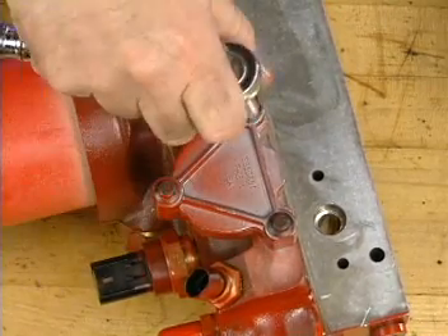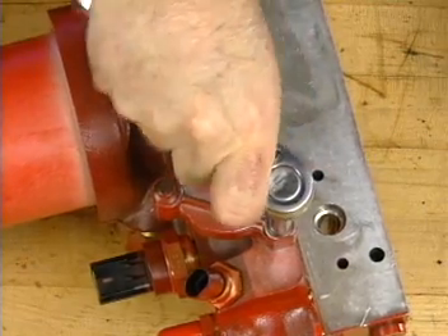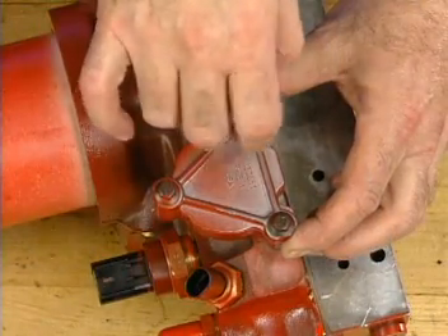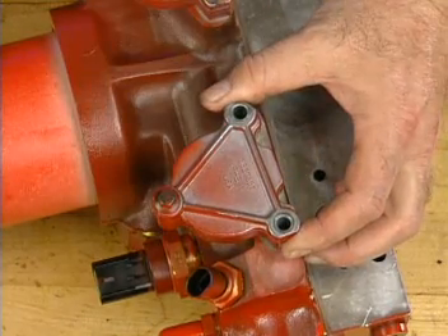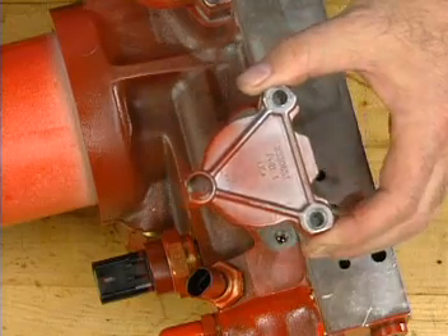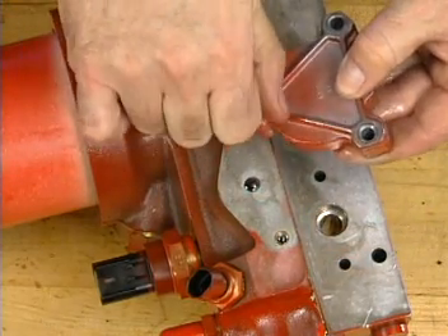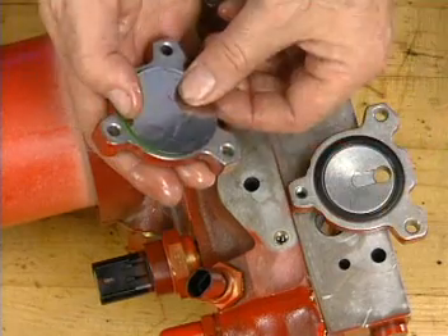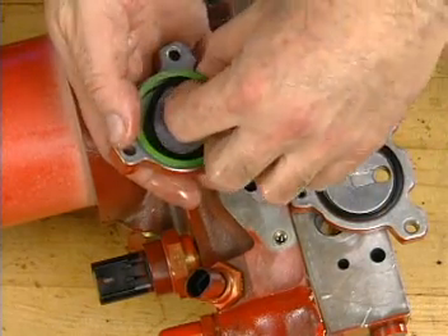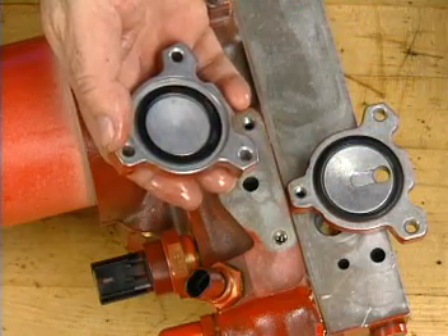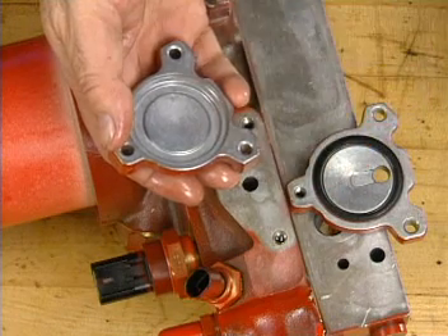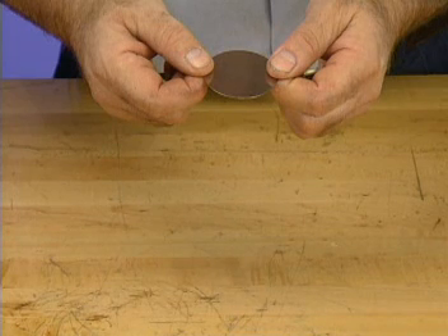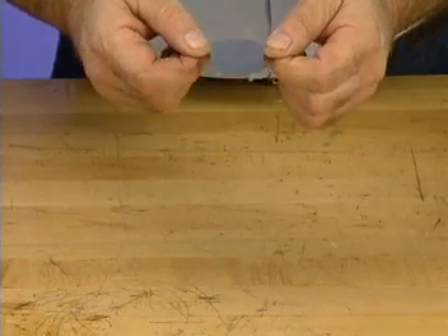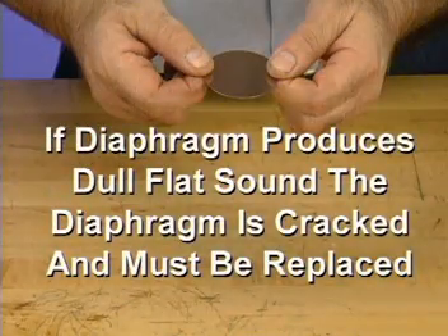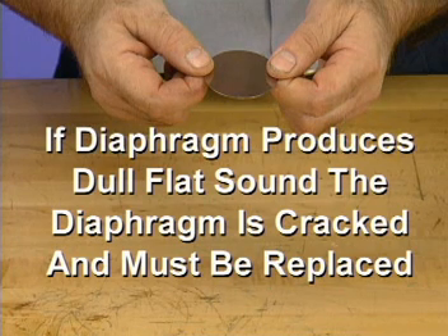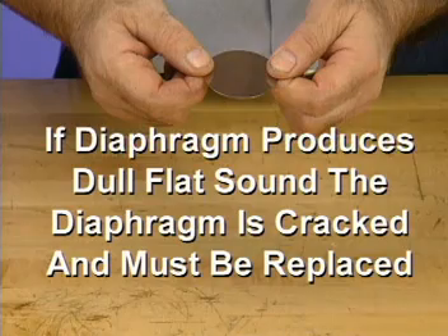Begin by loosening all 3 cap screws in the damper housing. Then remove the 2 cap screws that attach the damper assembly to the IFSM housing. Remove the 3rd cap screw and then remove the housing from the cover. Take out the spring steel diaphragm. Check for corrosion, wear, or damage and replace any parts that are unacceptable for reuse. The diaphragm is checked for hidden cracks by dropping it on a flat, hard surface. The diaphragm should have a clear ring. If the diaphragm produces a dull, flat sound when dropped, the diaphragm is cracked and must be replaced.